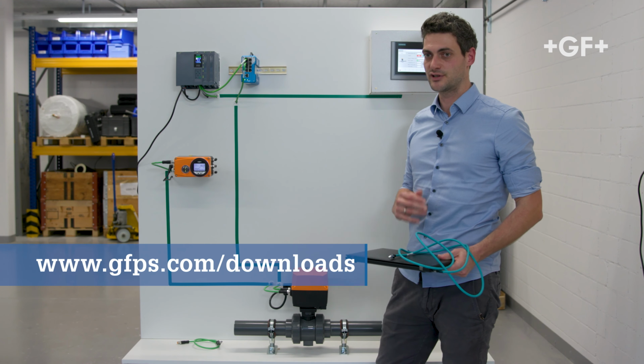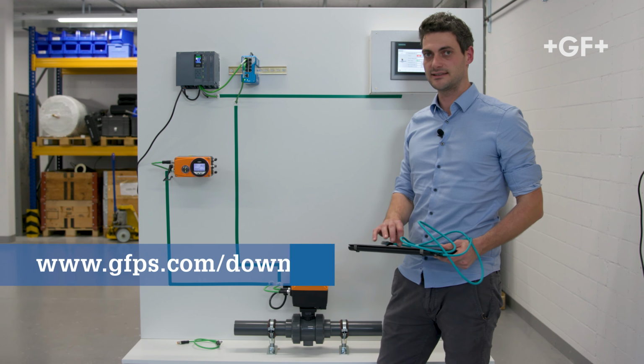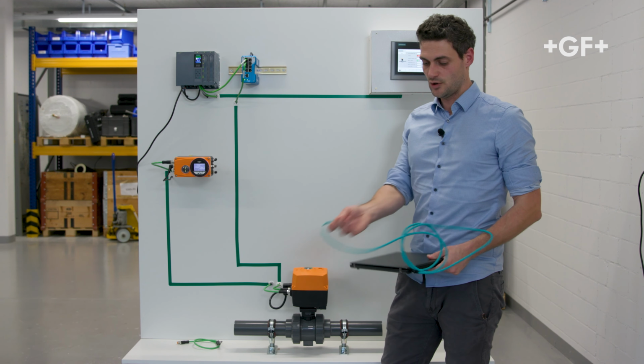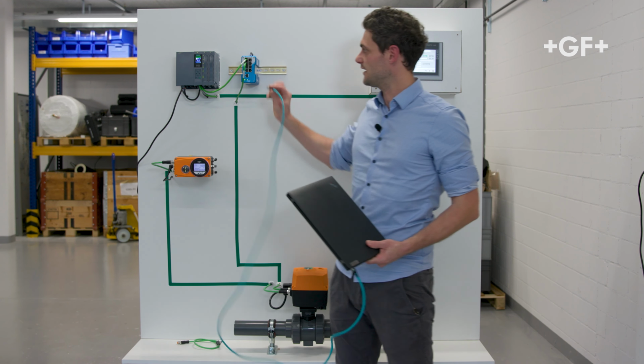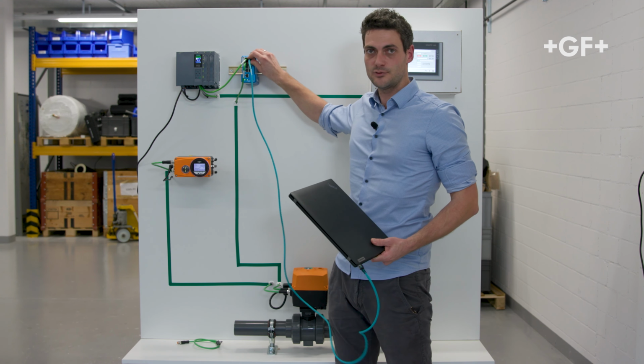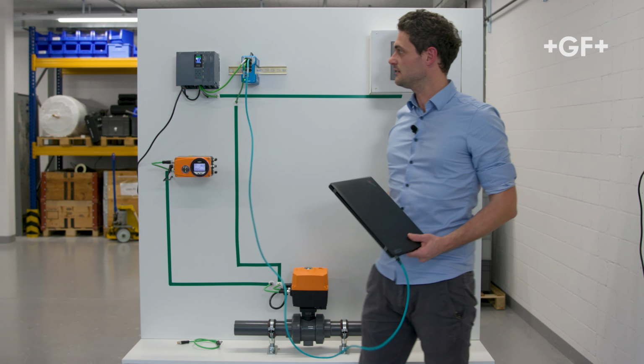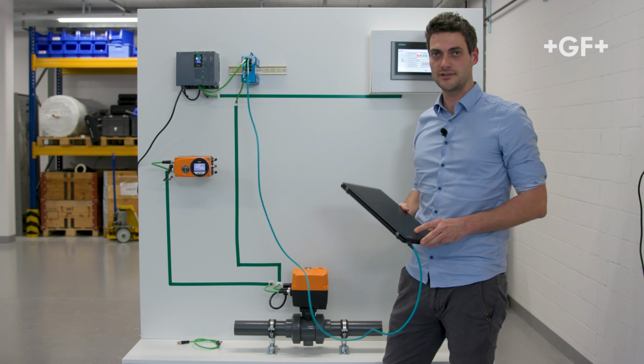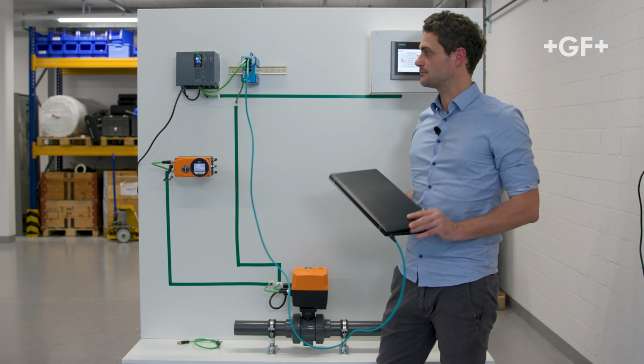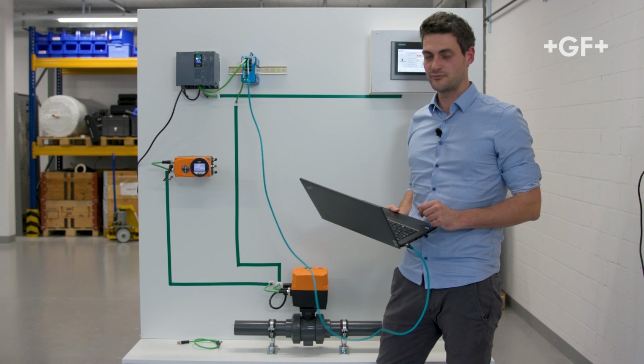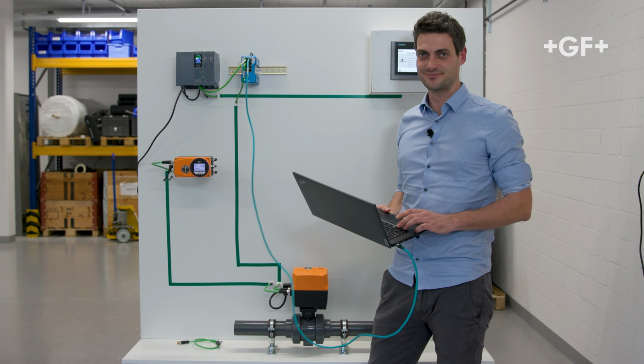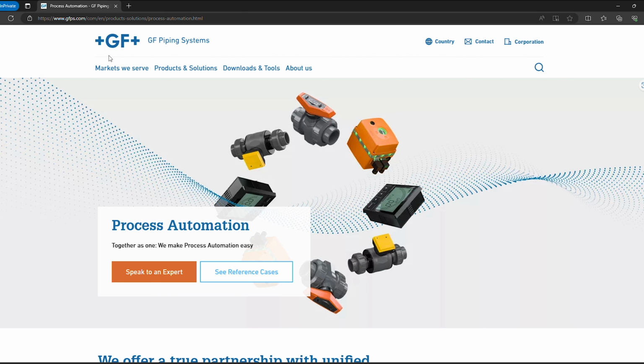Let's take a look at which capabilities are available in this web server. All I need for this is to connect to this local network, in this case by plugging into the Ethernet switch here. I have some open ports, and I need a normal laptop with a very simple web browser on it. Connect to the embedded web server. Enter the individual IP address of the electric actuator into a standard web browser.